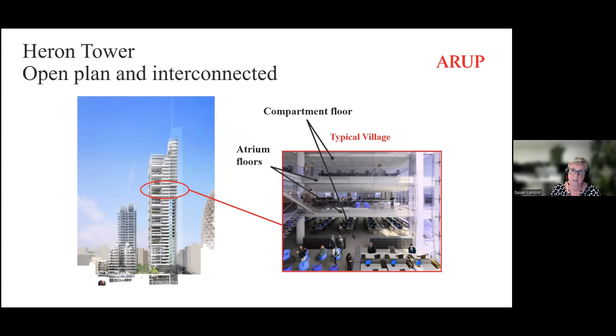This work in structural fire engineering continued with our investment into fire dynamics research for large open plan compartments. The tools we were using were limited to post-flashover fires in very small compartments of about 100 square meters or 1,000 square feet, like a typical hotel room. We knew they were not addressing real fires in large modern open plan offices.